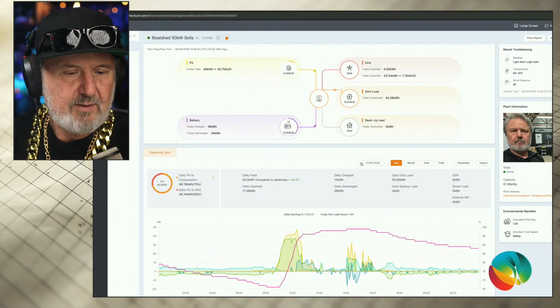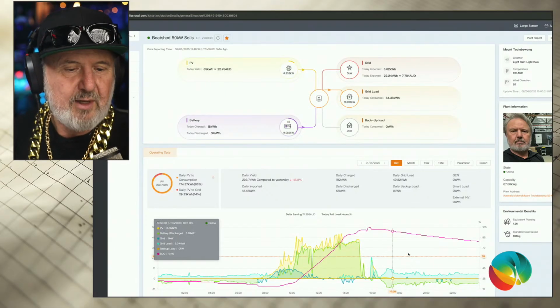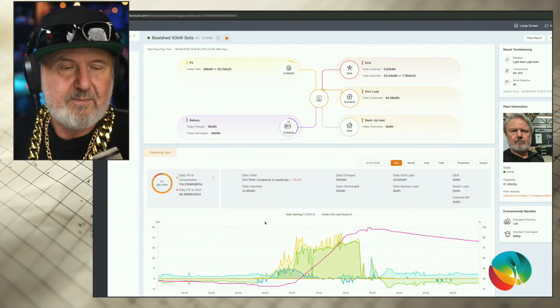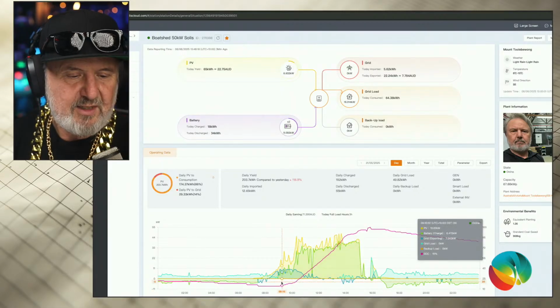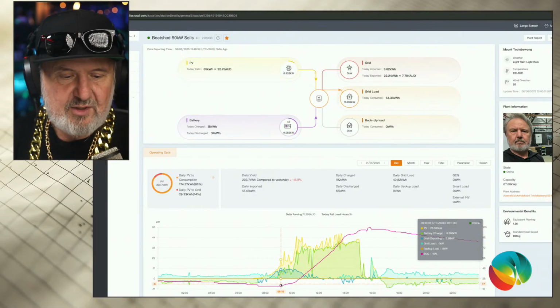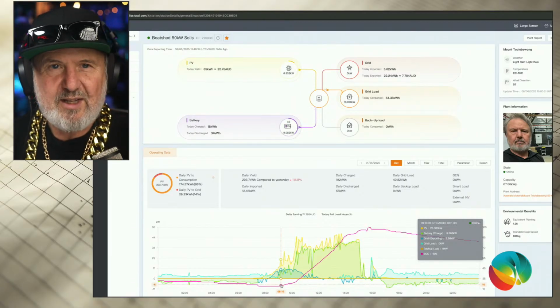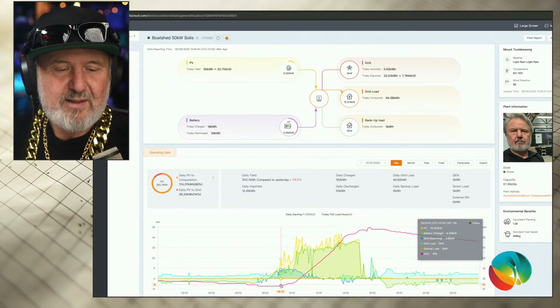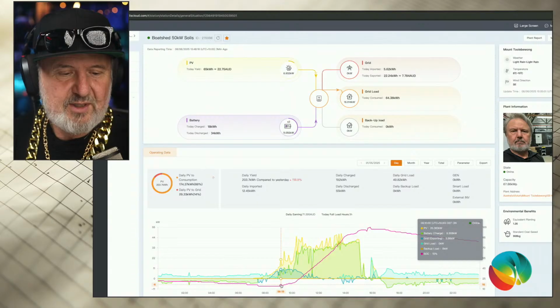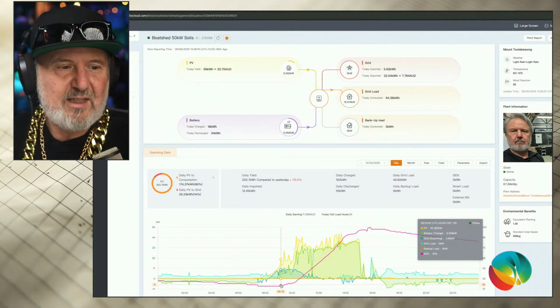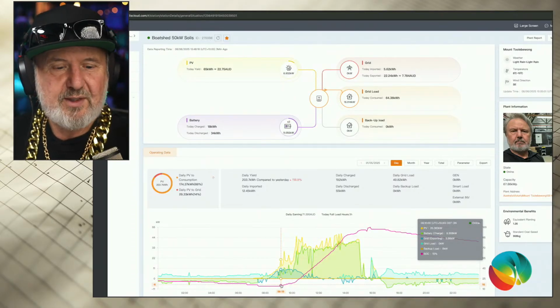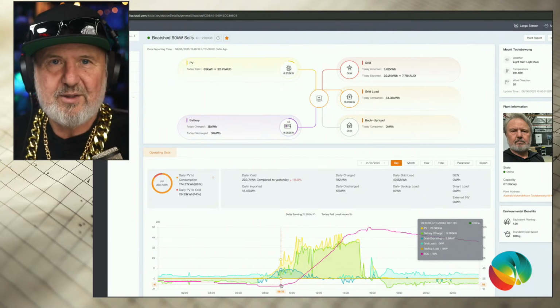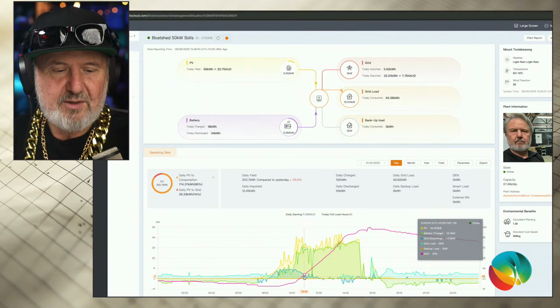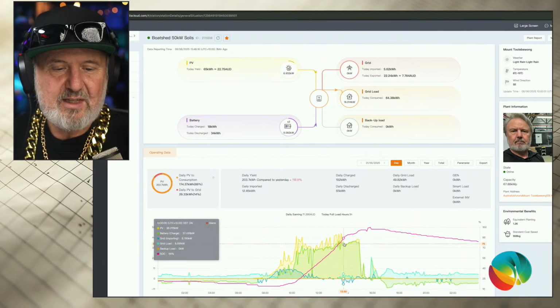Stop clicking, Glenn. There we go, so that down the bottom there is a good day. The red line is the state of charge, and you can see it's at 15%, which is the minimum I've set it to. You can go down to 10, but I like to give the batteries a little headroom to be sure. Once the sun comes out, there's a tracking 68 kilowatt array connected to the Solis inverter, and it just goes full power as soon as the sun hits it in the morning, hence this almost linear rise in state of charge.